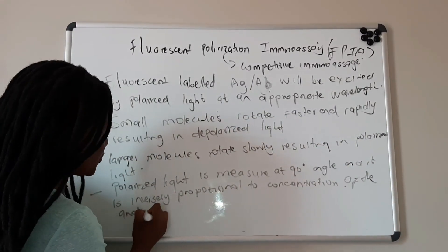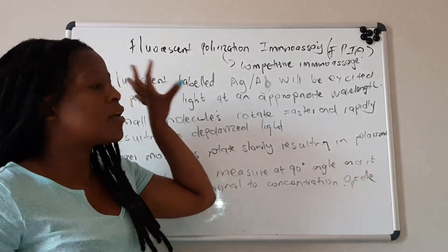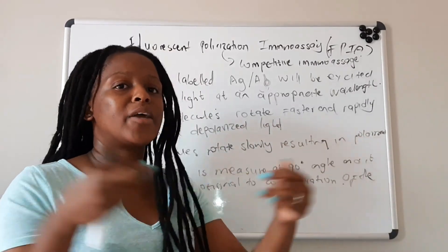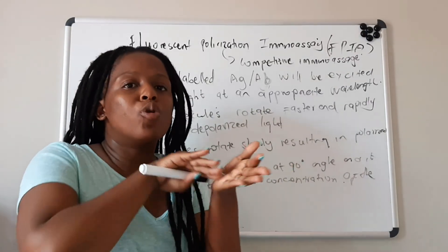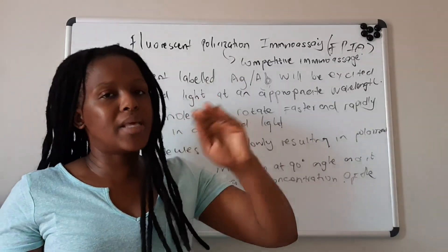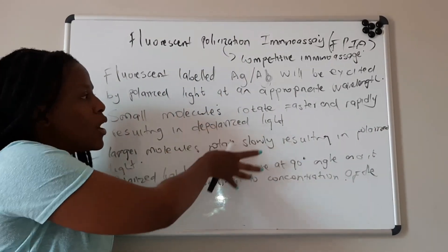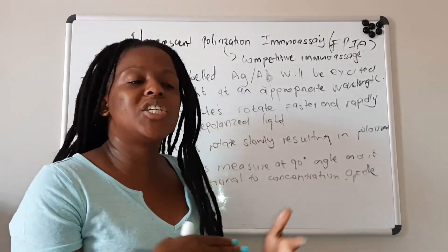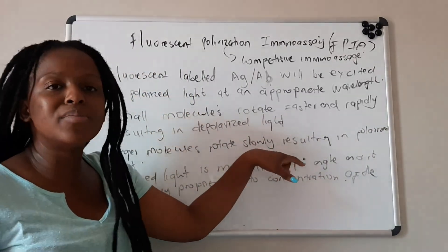How do we get this polarized light? Usually the polarized light is obtained when normal white light passes through special filters, which polarize the light. The light that reaches the cuvette is then polarized. Depending on whether the molecules are smaller or larger, the smaller ones will rotate rapidly and change the plane of that polarized light — that is why we say the light becomes depolarized.